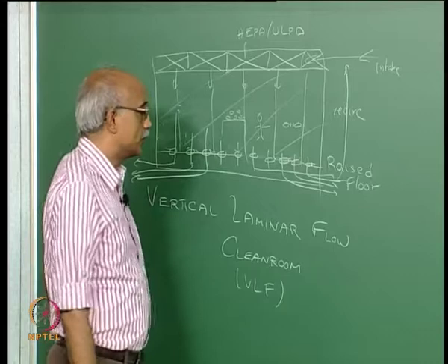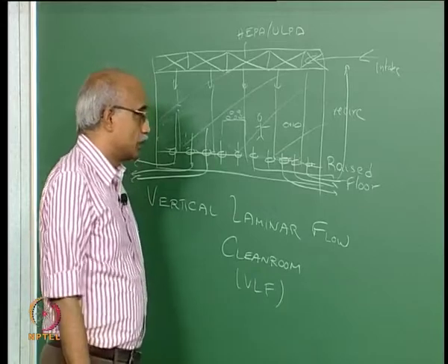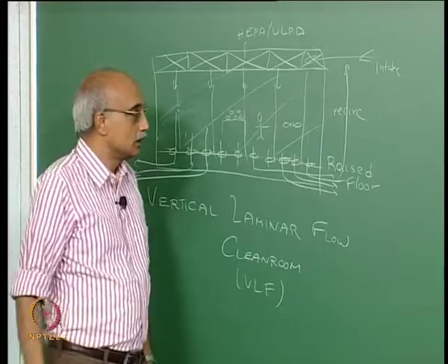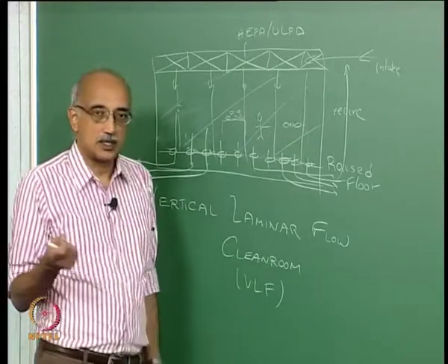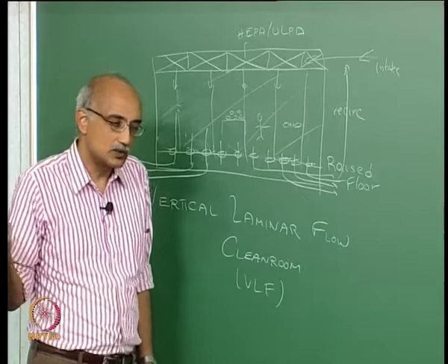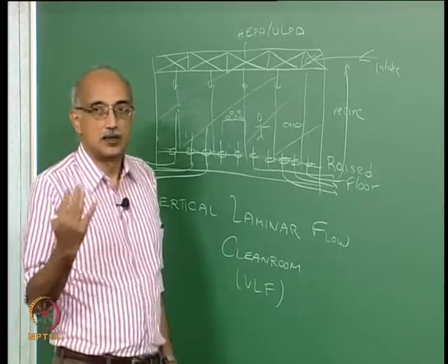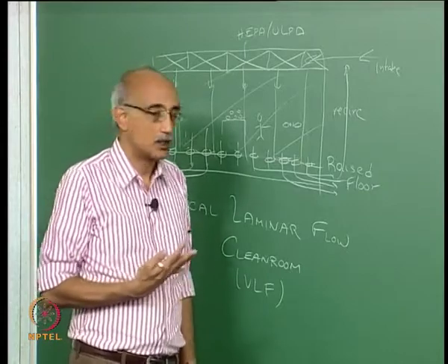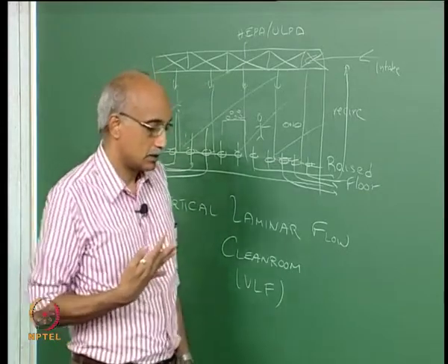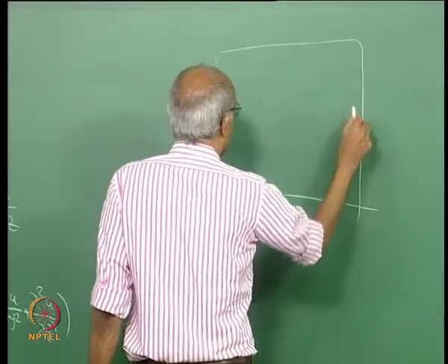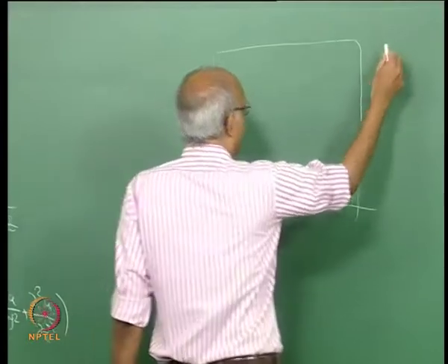The other assumption you can make is that all the flow rates are essentially in steady state, constant flow rates. You can also assume that concentrations are not varying with time. So, essentially you can simulate a quasi-steady approximation to the operation of a clean room. Now, when you do that, the picture is going to look like this. Again, you have the clean room and you have particles coming in.